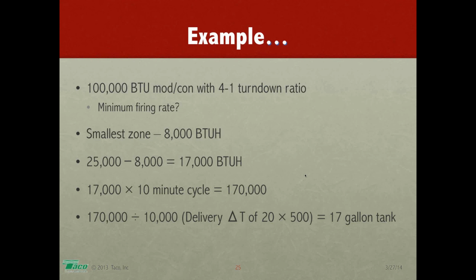If you can find a 20-gallon tank instead of a 17-gallon tank, well, you put in a 20-gallon tank. Worst thing that's going to happen there is your minimum run time might be 11 or 12 minutes. Not a bad thing. The bigger the tank, the better off we're going to be in terms of minimum run time. And you don't have to go crazy on the tank. Here, anything between a 15 and a 20-gallon tank is going to be just fine. It's going to be a heck of a lot better than not doing anything. That's the point we're trying to make here. So that'll do it for the presentation.